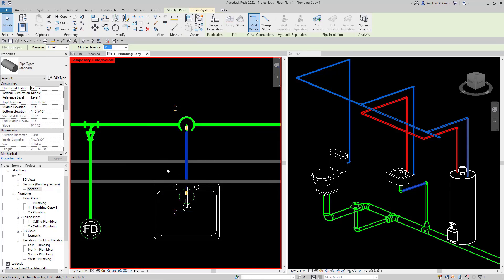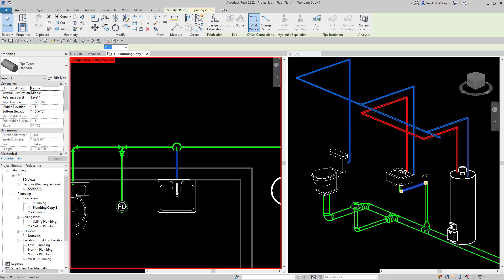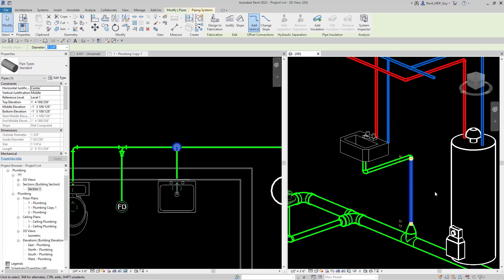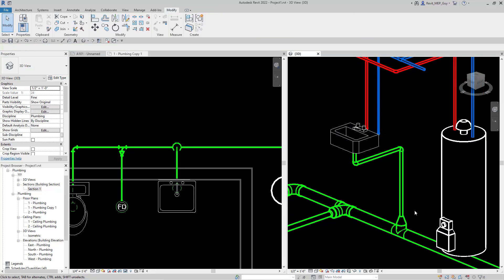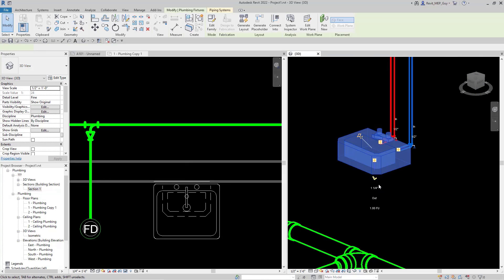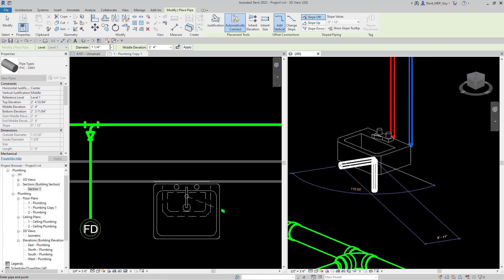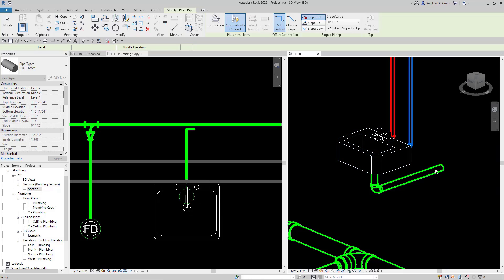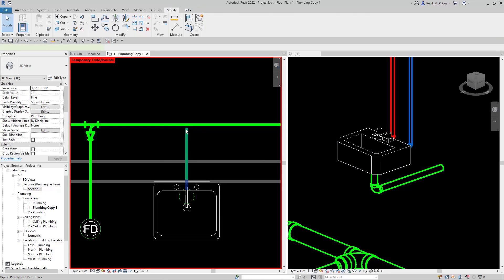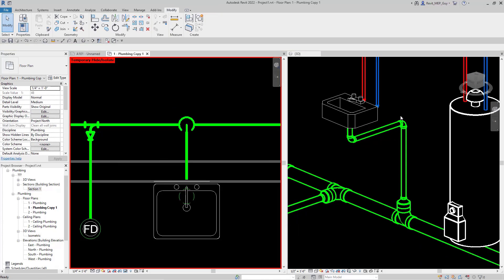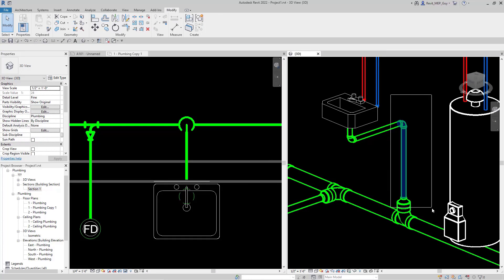Zooming in, I notice the fitting wasn't correct — it's showing pipe type Standard, not PVC. So I need to undo all that piping. This time let's make sure we're using the correct pipe type — go to PVC. We'll drop it down again to 18 inches (one foot six), hold Shift, go to here, hit escape, then drop it right into the main. We should get the right fittings this time. That's looking much better. I'm actually going to upsize this piece of pipe right here to two inches — select it and change it to two inches.